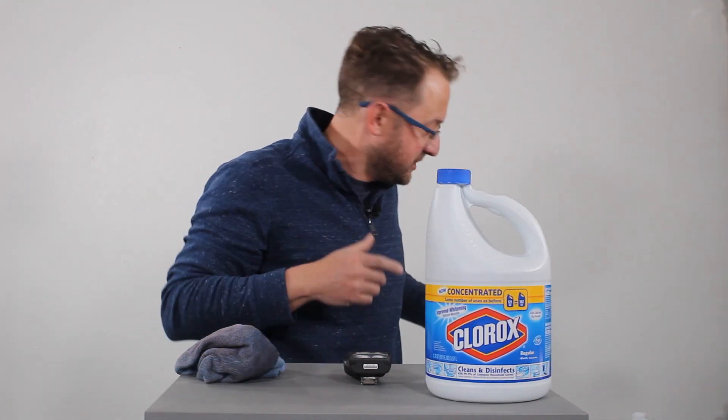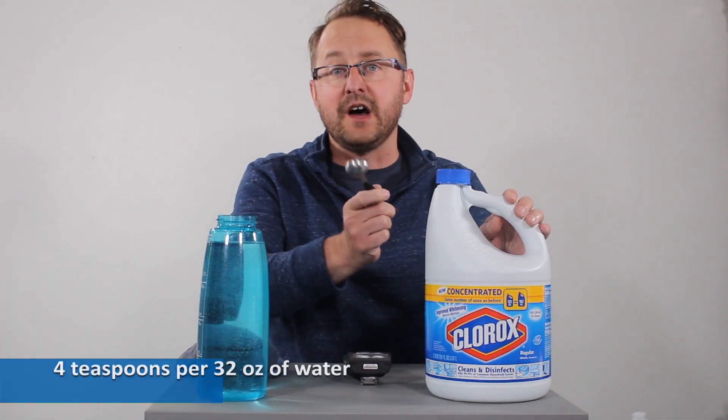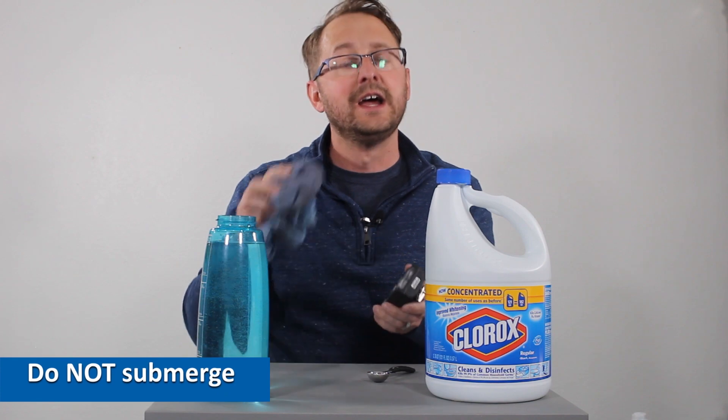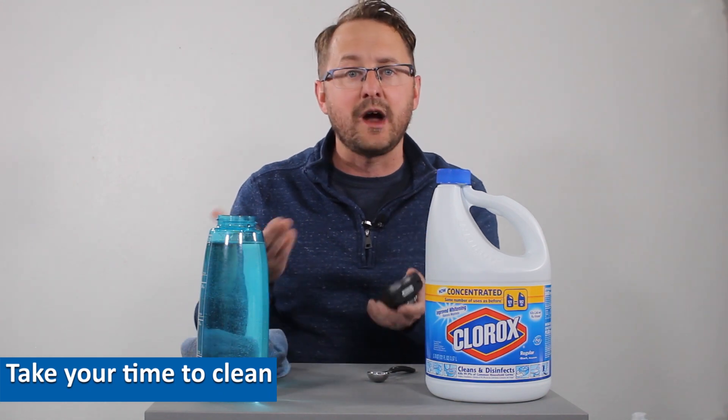So what do we advise to sanitize a gas detector? Here we've got a bleach mix — we take bleach and water. We recommend four teaspoons of bleach mixed with about 32 ounces of water. Same principles apply as cleaning: use a damp rag, wipe it over the monitor itself, and make sure you're getting all those corners.